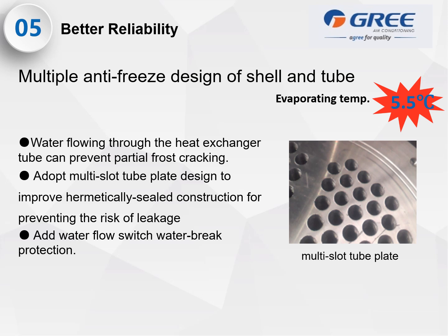Multiple anti-freeze design of shell and tube. Evaporating temperature is 5.5 degrees C. So, water flowing through the heat exchanger tube can prevent partial frost cracking. Adopt a multi-slot tube plate design to improve hermetically sealed construction for preventing the risk of leakage, and it also add water flow switch or water break protection.